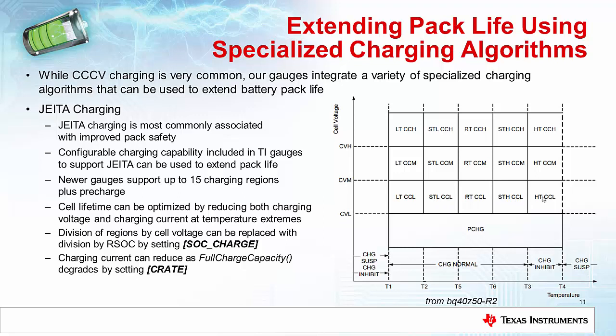And so what you can do is try to set these up such that, say you're at low voltage and you want to charge fast, so you're at lower temperature, and you allow a lot of charging. That starts heating things up and it moves you into higher temperature ranges. If you start getting into higher temperature ranges, then you can start relaxing back on your charging voltage and charging current settings such that as you continue charging, you don't generate quite so much heat. So you slow down the rate of charging some, but it reduces the heat that you're generating, and you tend to be pushed back over into these regions when you're actually charging the battery. So if you optimize these based on your use condition, you can reduce how much heat the battery generates during charging, and how much time it sits there at high temperature while it's at a high voltage or a high RSOC level.